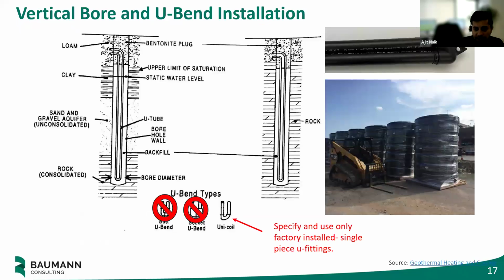A few notes on boreholes and construction. Now that we've seen that video, they're big holes in the ground. You put the tubes down and fill it up with grout, which can be bentonite, cementitious, really anything. These boreholes typically go about 250 to 600 feet in the DC region, depending on geology and what makes sense for drilling. You want to avoid changing your drilling methods partway. I showed you the most predominant one, but there are other methods. You don't use the same bit to drill in bedrock as you do in soft silt, but typically 250 to 600 feet is about how deep you see in DC.